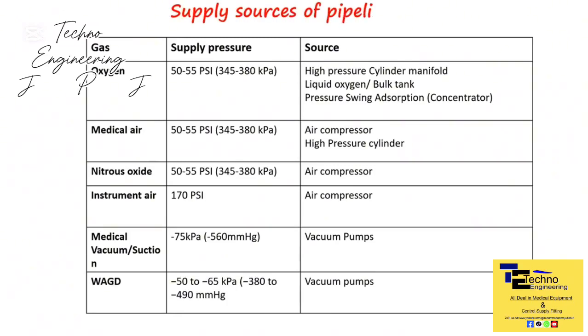Oxygen is supplied at a pressure of 50 to 55 psi from either high-pressure cylinder manifold, liquid oxygen tanks or the combination of both. In areas where a bulk system or high-pressure cylinder manifold is not suitable, oxygen may be supplied by an oxygen concentrator. However, on-site production of oxygen through pressure swing adsorption is still a relatively new technology.